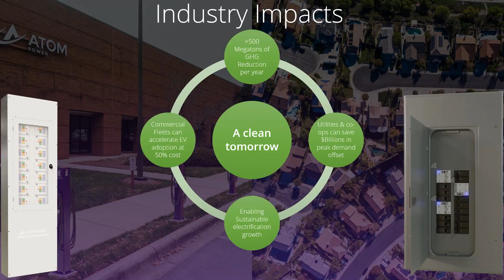Going into a little more detail now, I'll go back to our circuit breaker and how that works within the power distribution network. So how is a solid state circuit breaker different than what you'd find in a traditional circuit breaker today? A traditional circuit breaker uses protection based off of normally two components, a thermal and a magnetic. The thermal is based off of when current is flowing through the breaker, it heats up, and there's a bimetallic strip in there, and as it heats up, it'll bend that bimetal, which causes it to pop open and trip the breaker.